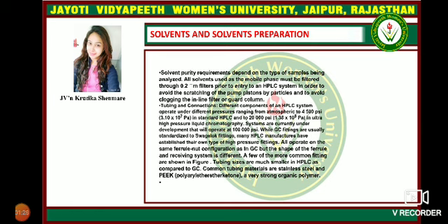The solvent and solvent preparation. Now, how is the solvent prepared? The solvent purity requirements depend on the type of sample being analyzed. All solvents used as the mobile phase must be filtered through a 0.2 micrometer filter prior to entry to an HPLC system in order to avoid the scratching of the pump pistons by particles and to avoid clogging in the inline filter or guard column.